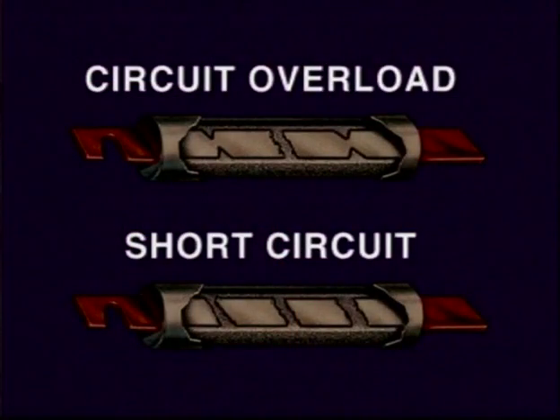If, during troubleshooting, a fuse is found to be open, it's a good idea to have it cut in half with a saw and determine if the cause of the opening was due to a short circuit or an overload. This could help tremendously to determine the source of a problem.